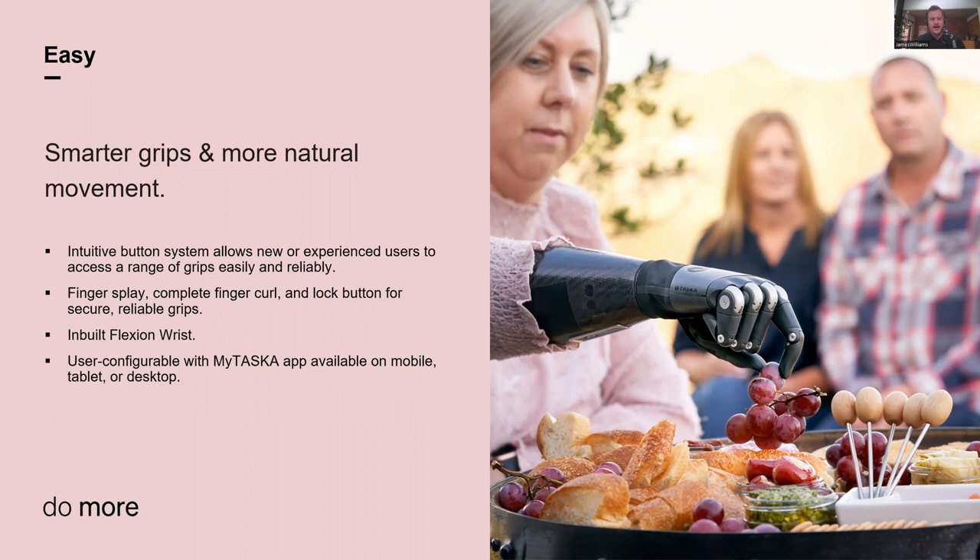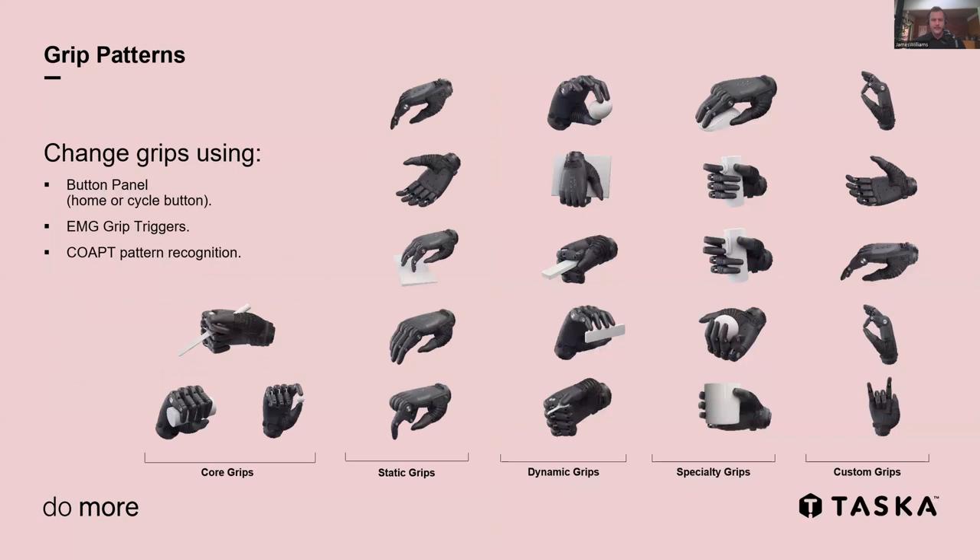We've also got our MyTASKA app, available on mobile, tablet, and desktop, so both patients and clinicians can configure the hand across a range of platforms. Multi-articulating hands mean a range of grips — we have 23 grips available, ranging from core grips through to a bunch of different options. We even have five customizable grips that prosthetists or patients can modify themselves. To change grips, you can use the button panel, EMG grip triggers, co-contract, double pulse, long holds, or various grip change methods. We're also compatible with a range of pattern recognition systems — for people in Australia, the COAPT is a really good combination with the Tasker.